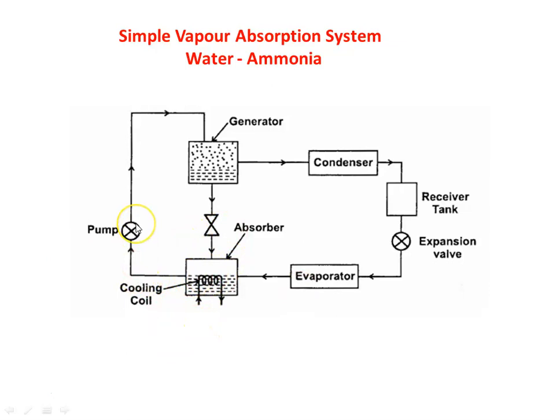Then the solution goes through the pump to the generator. In the generator, we have a heating element which heats the ammonia-water solution. When the solution is heated, ammonia evaporates and ammonia vapor is formed. This vapor goes to the condenser. As the ammonia vapor is removed from the solution, it becomes a weak ammonia solution, which is brought back to the absorber.